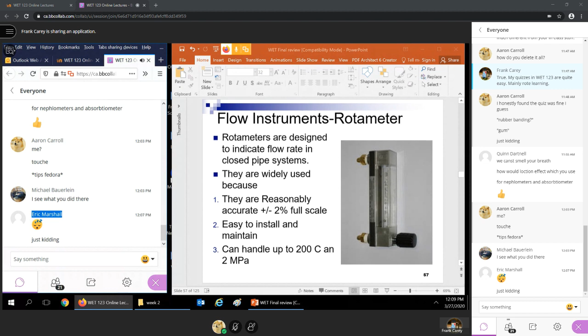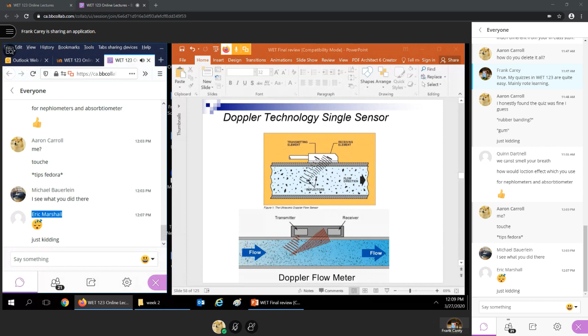Doppler technology, I talked about strap-on ultrasonic flow sensors. They can have fixed flow sensors. They would never be mounted on the top; they'd always be mounted at 3 o'clock or 9 o'clock. So you have to know that, and also know that there have to be particles inside for Doppler to work.